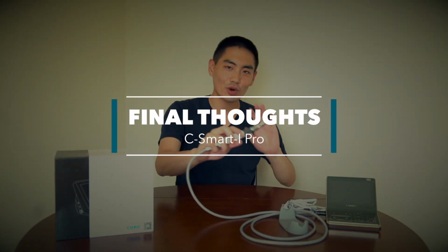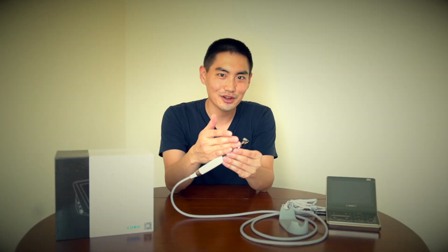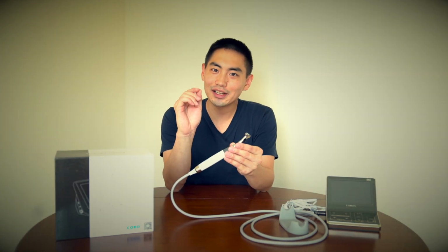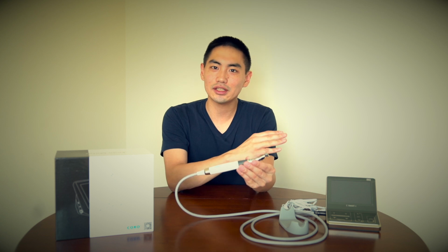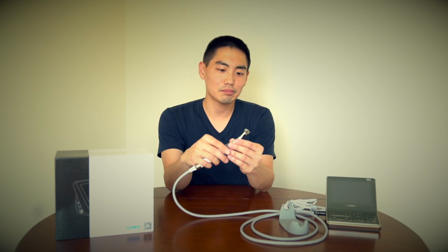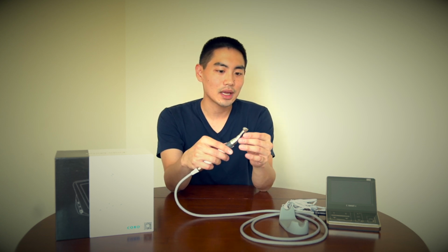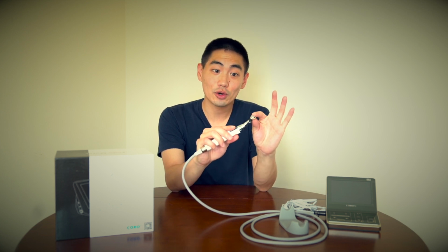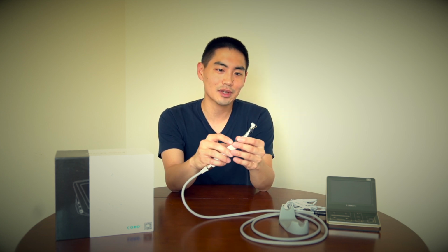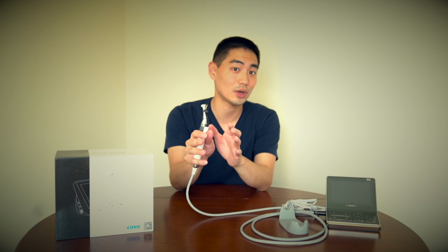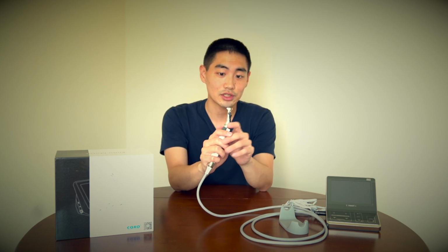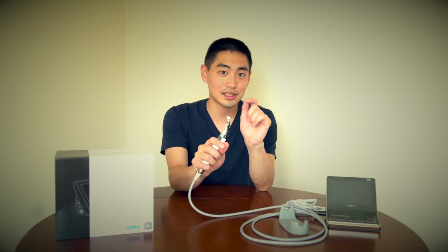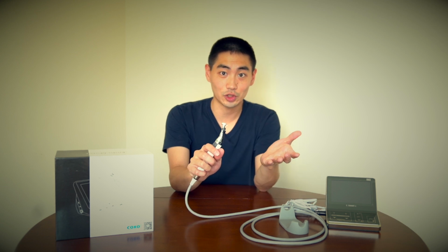If I have to nitpick a couple of things, these are small nuances. The first is the sound of the head - it's a little on the louder side. Not much louder than the average handpiece, but it could be a bit quieter. At the same time, it is micro-sized, which I like, because sometimes with a latch-type attachment it takes up more of the file, leaving less room for the stopper if you choose not to use the 2-in-1 apex locator function. With a smaller head, you can see more, and it's easier to use reference points in certain circumstances.